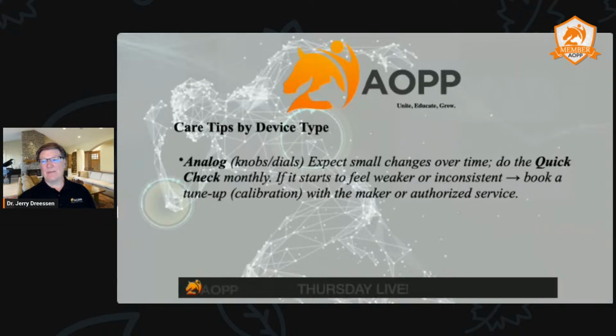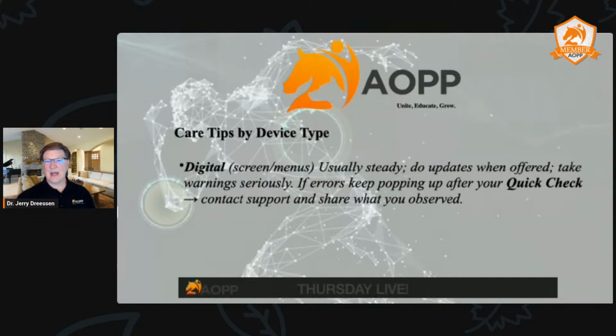Check it monthly, do the quick check monthly. And if it starts to feel weaker or inconsistent, book a tune-up calibration with the maker or authorized services. Some of them you pack up and ship, and then they recalibrate it and send it back. Find out what that turnaround time is. Know what that is now, like if I were to send this in to get recalibrated, what's my wait time? Because if all of a sudden you need to do that, at least you know it's a 10-day turnaround or a 5-day turnaround, or they'll send you a device to use while yours is under maintenance, getting tuned up. So those are important things to know ahead of time if you need to use that.